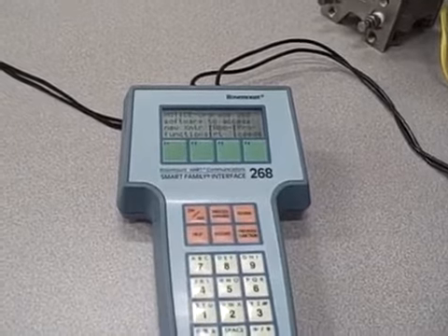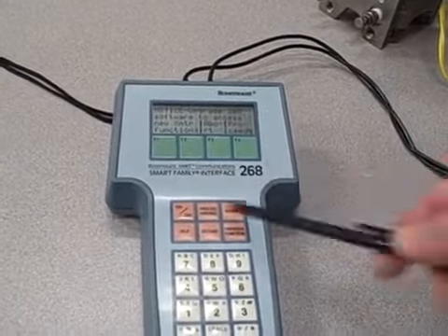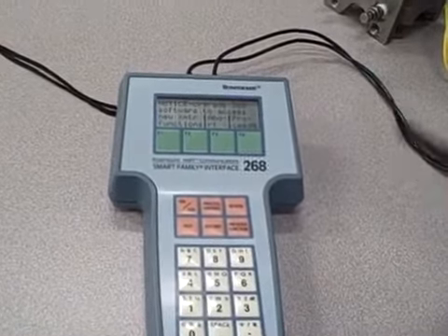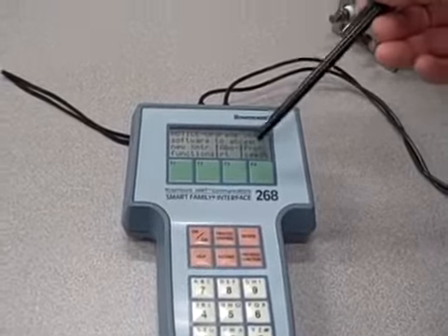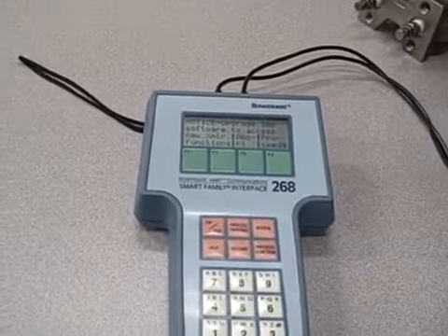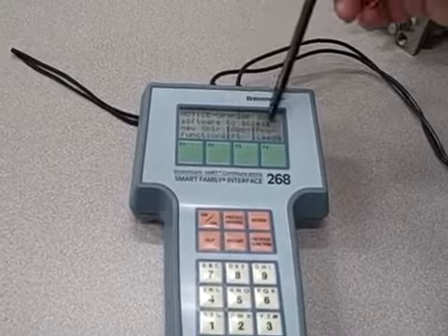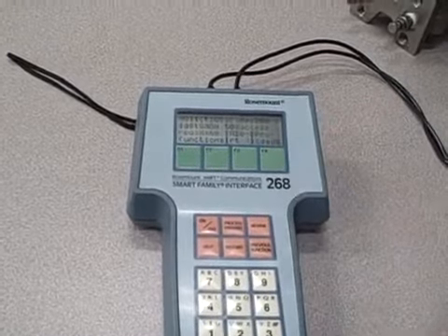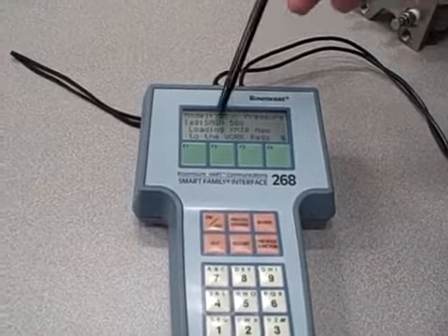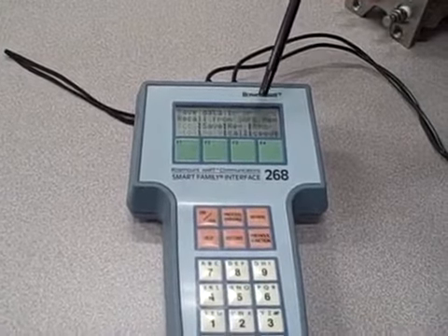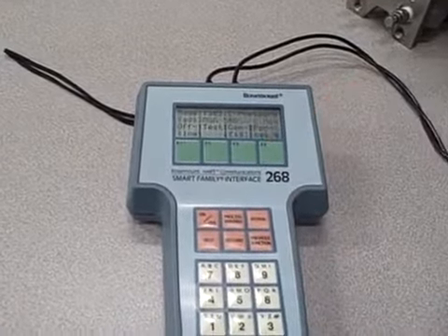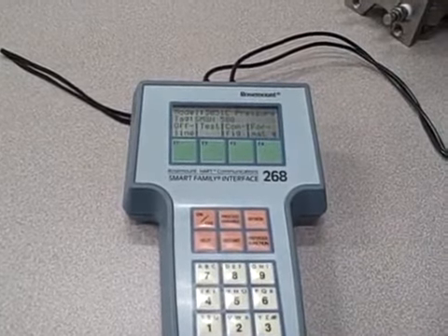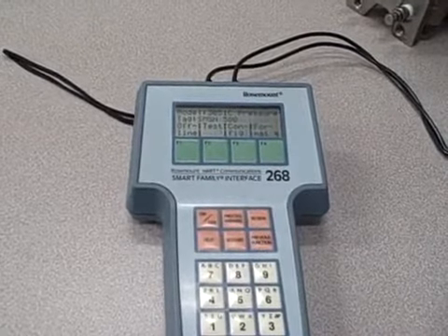And here we have a case of this. This Model 268, which is a rather dated communicator, simply does not have the necessary device description files to talk to this transmitter. And it tells us, upgrade 268 software to access new transmitter functions. If I try proceeding, it does recognize what the transmitter is.